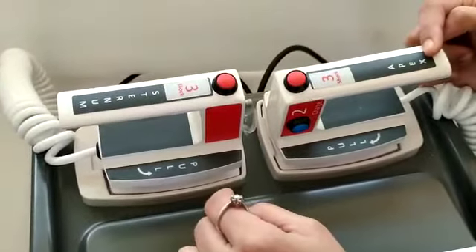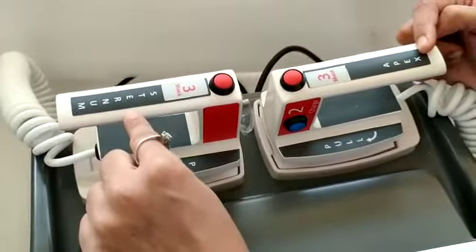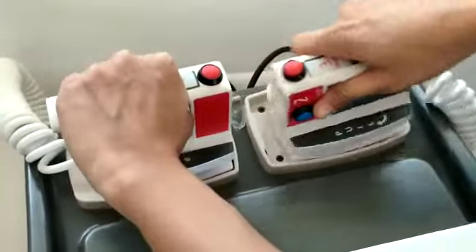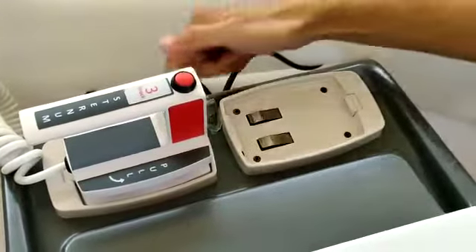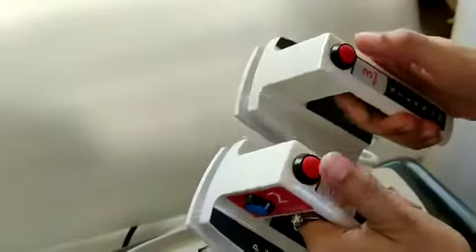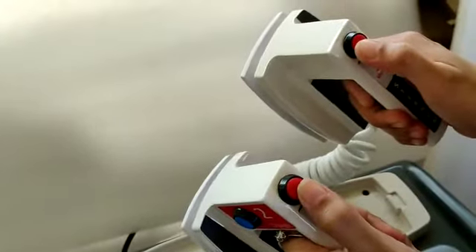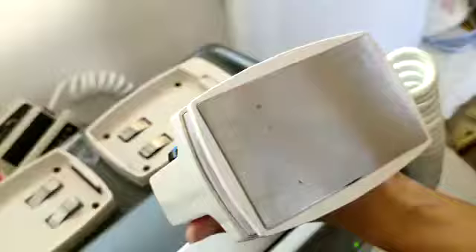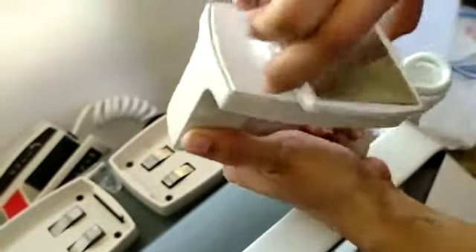These are the paddles. This is for the apex position. This is for the sternum position, and it is placed in this cradle. These are the cradles. This switch, and to discharge the shock, the user needs to press both together. This can be used for adult, and to use it in pediatric you have to use this.